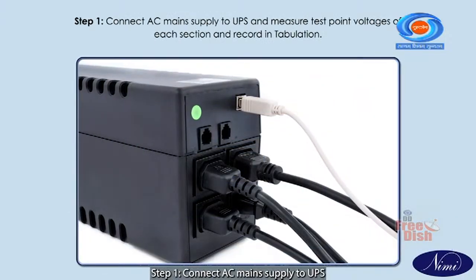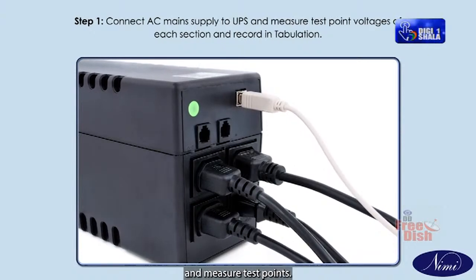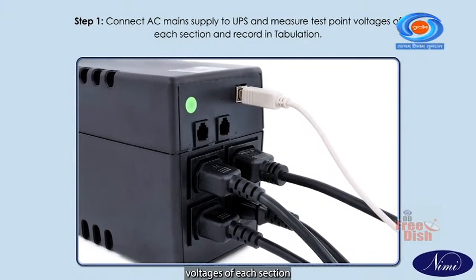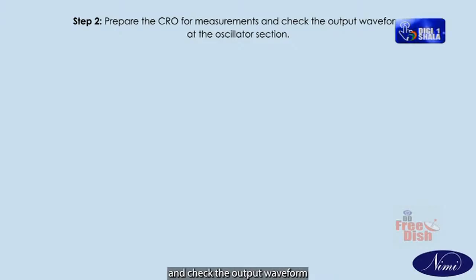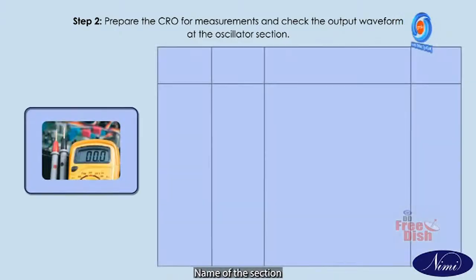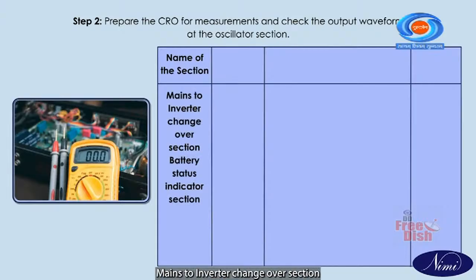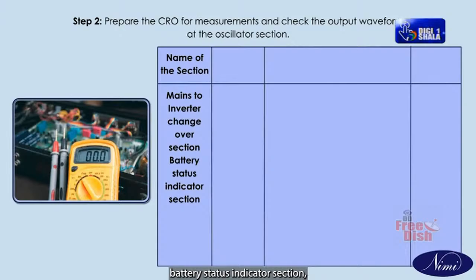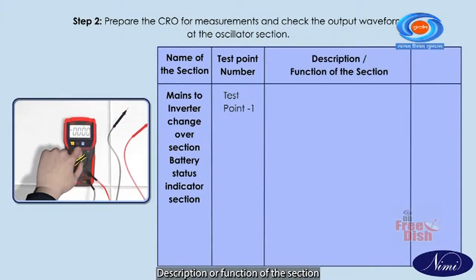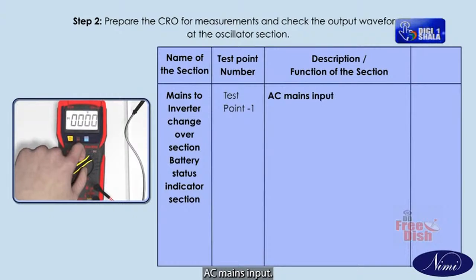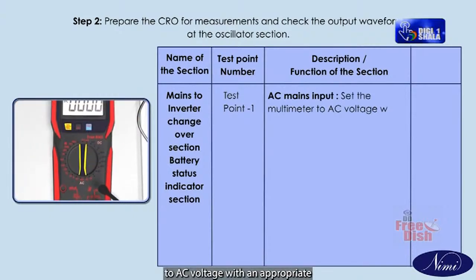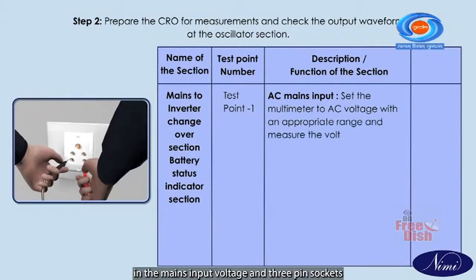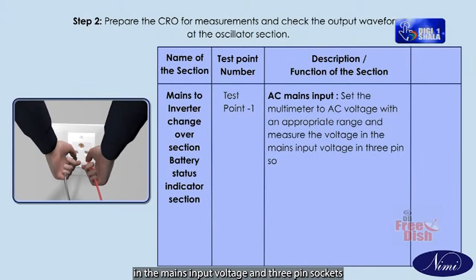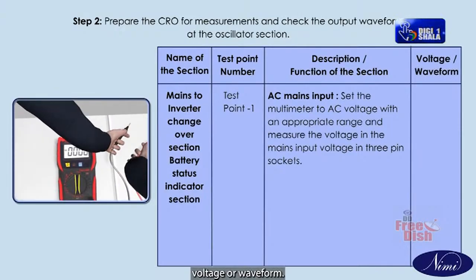Step 1. Connect AC main supply to UPS and measure test points voltages of each section and record in tabulation. Step 2. Prepare the CRO for measurements and check the output waveform at the oscillator section. Name of the section: mains to inverter change over section, battery status, indicator section. Test point 1. Description or function of the section: AC mains input. Set the multimeter to AC voltage with an appropriate range and measure the voltage in the mains input voltage in 3-pin sockets. Voltage or waveform.